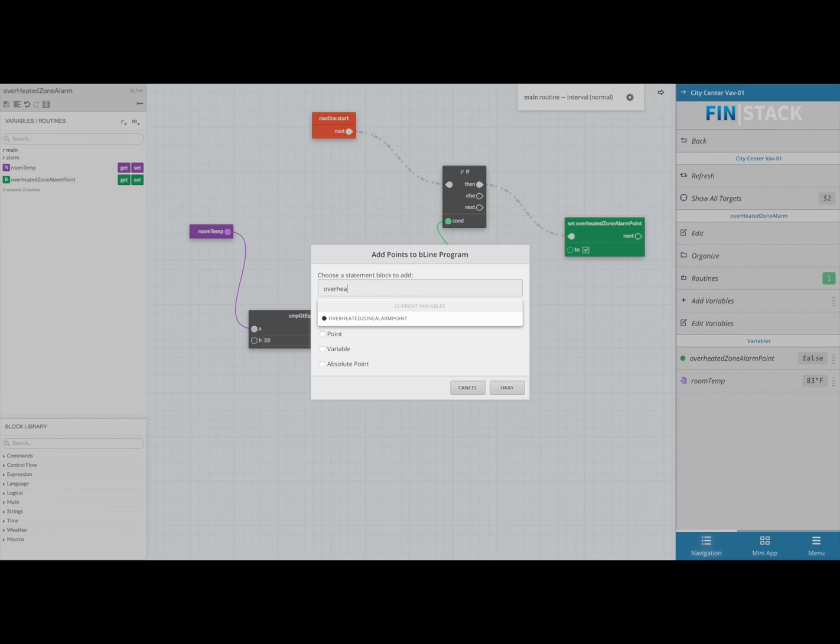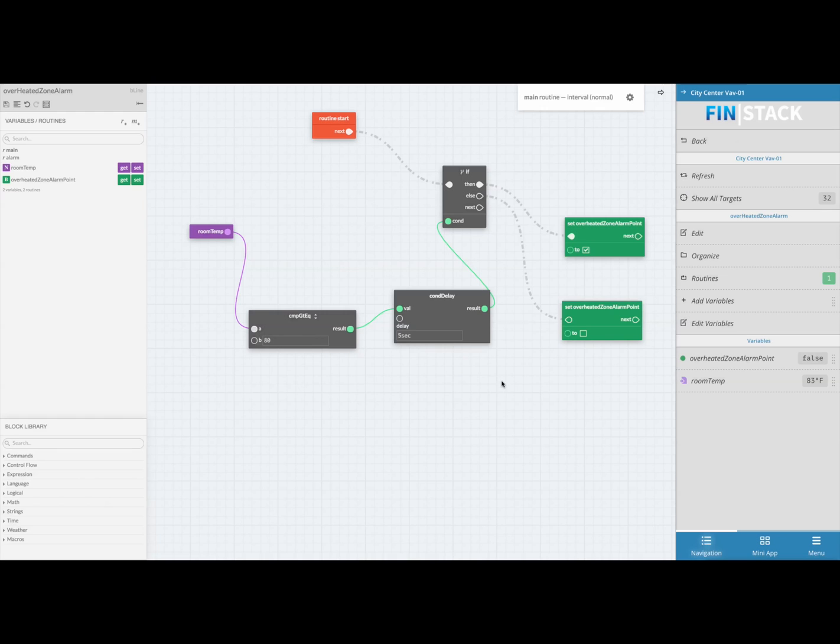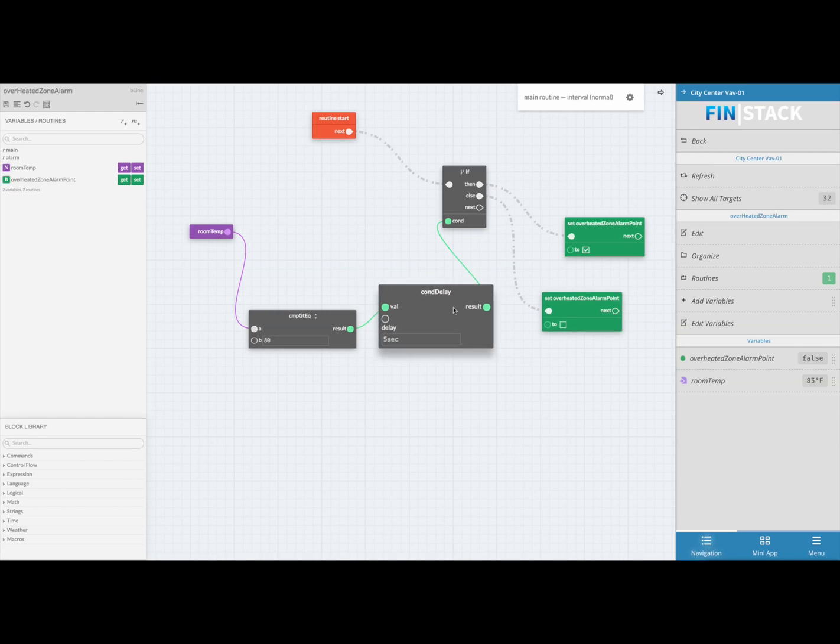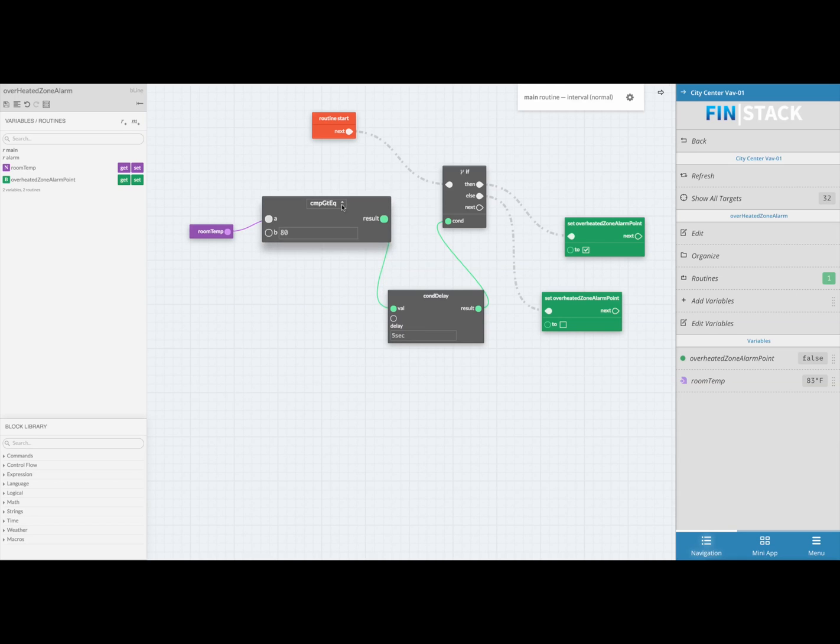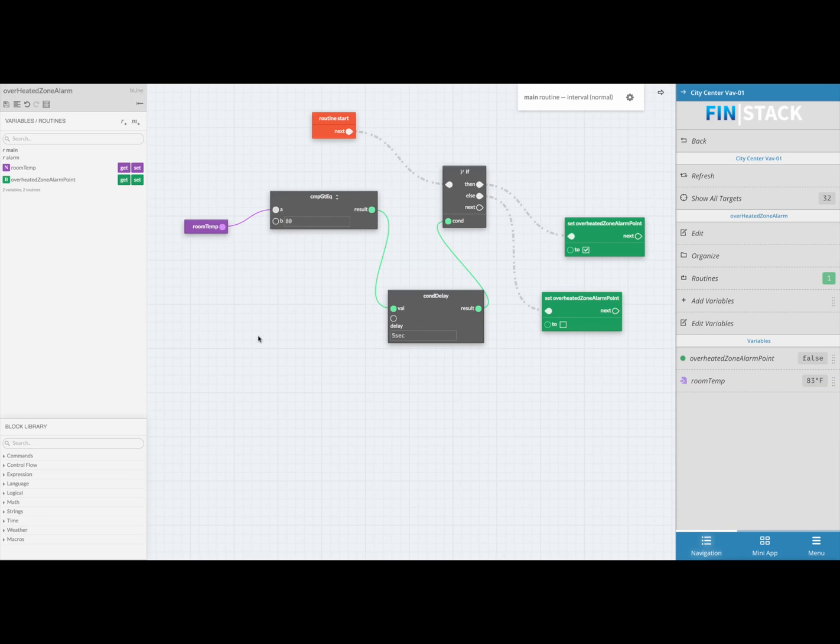If we were to read this from start to finish, it would read: if the room temp of this equipment is greater than or equal to 80 for more than five seconds, then set the overheated zone alarm point to on. If not, then set the alarm point to off.